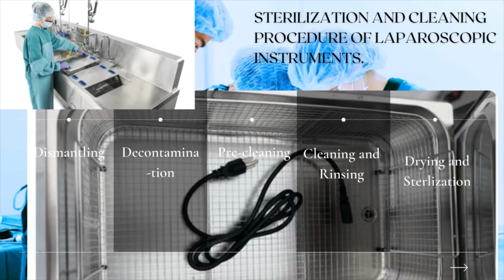The cleaning process includes washing the instruments with soap, but this is not effective compared to enzymatic and detergent-based cleaners. Use of soft brushes on the laparoscopic instrument results in thorough cleaning. Next is rinsing. Laparoscopic instruments are best rinsed in running water so that all particulate matter, as well as residues of chemicals used for decontamination and cleaning, are completely cleared from them. The usage of running water is far better than rinsing them in stagnant water.